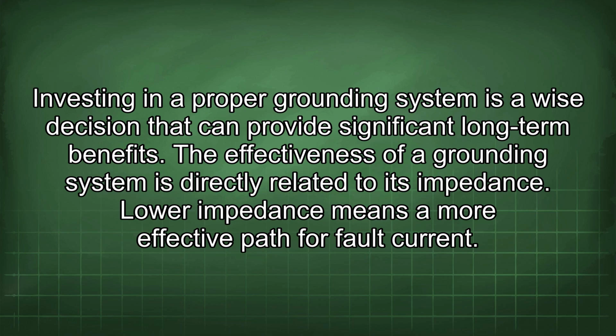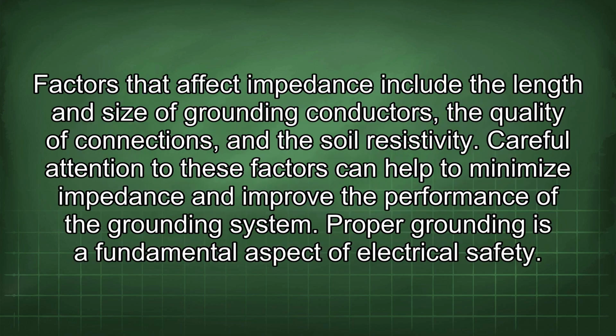The effectiveness of a grounding system is directly related to its impedance. Lower impedance means a more effective path for fault current. Factors that affect impedance include the length and size of grounding conductors, the quality of connections, and the soil resistivity. Careful attention to these factors can help to minimize impedance and improve the performance of the grounding system.